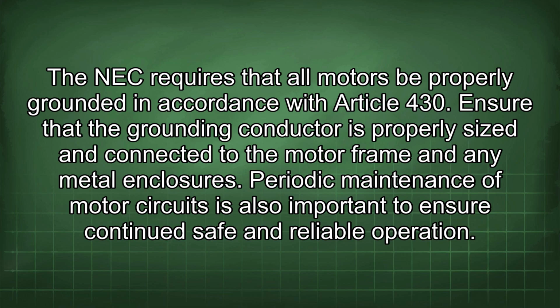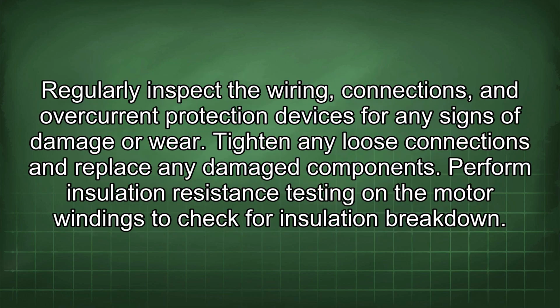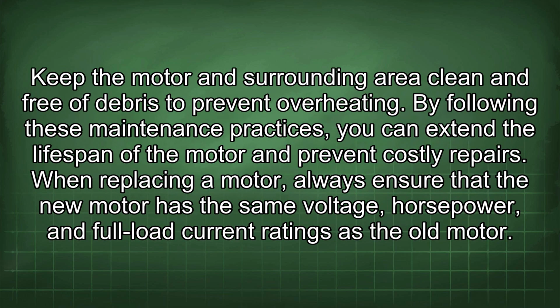Periodic maintenance of motor circuits is also important to ensure continued safe and reliable operation. Regularly inspect the wiring, connections, and overcurrent protection devices for any signs of damage or wear. Tighten any loose connections and replace any damaged components. Perform insulation resistance testing on the motor windings to check for insulation breakdown. Keep the motor and surrounding area clean and free of debris to prevent overheating. By following these maintenance practices, you can extend the lifespan of the motor and prevent costly repairs.